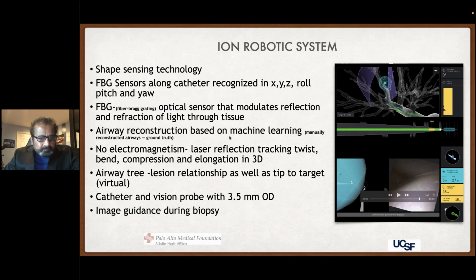So the fiber Bragg grating sensor picks up the light that goes through the sensor, and it measures twist, bend, and compression elongation. Now, this was originally designed to check the integrity of catheters, and it was actually not an Intuitive product. It was a product of Luna Medical, which was acquired by Intuitive and then superimposed on the system that they were already working on.